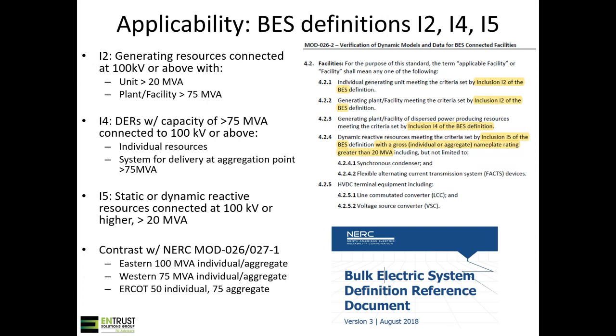First, we'll talk about applicability, which a lot of generator owners and transmission owners are heavily concerned about. The previous standards really just had MVA levels, and the Eastern Interconnection was pretty lax. Now, tying definitions to I2 for synchronous machines, any unit greater than 20 MVA connected to 100 kV or above, or a plant at 75 MVA or above—for the Eastern Interconnection, that's a big difference.